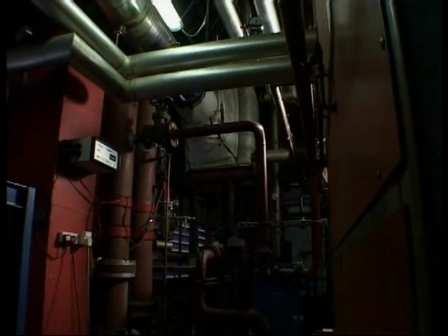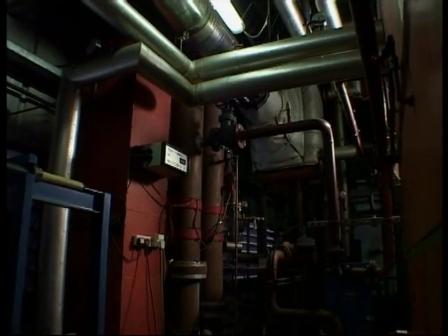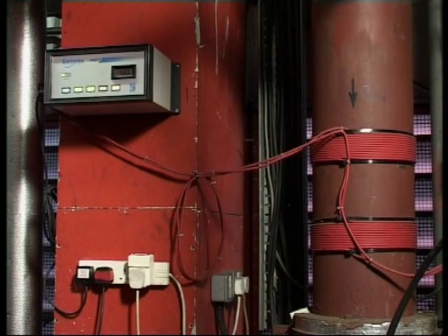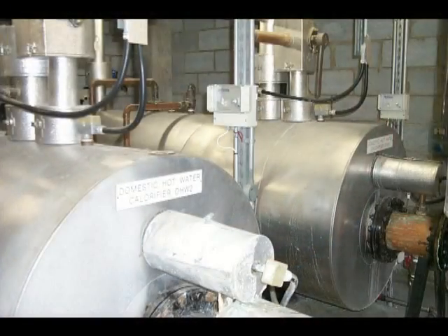I've been involved in testing and comparing the performance of water treatment devices, all the different types: electronic, electrochemical, softeners, dosing devices, essentially to benchmark performance and compare how well they perform in the field. In my opinion, electronic devices do perform very well. They do the job, especially when they're applied correctly. In the tests I've carried out, the results show that they improve anti-scaling performance 5 times in laboratory field trials, so it takes 5 times as long for scale to form, and that is translated into real benefits in the field.